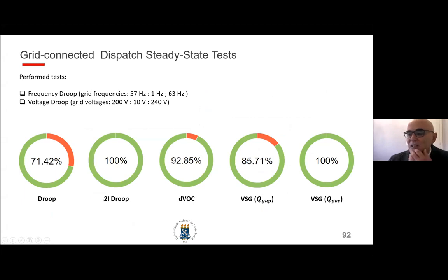We see that the droop with two integrators has one of the best results. The DVOC is not bad as well. There is a failure here, but if you look at the result, when you see one that fails, you have to investigate how significant it is—is there a way to change some parameter and make it pass the test?